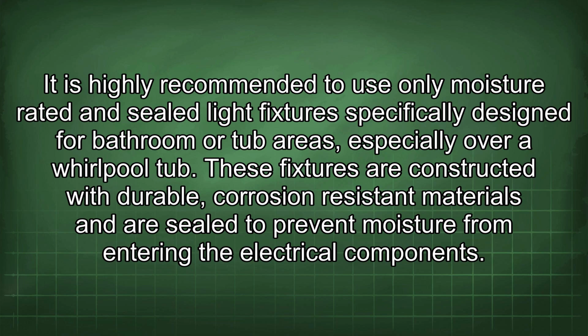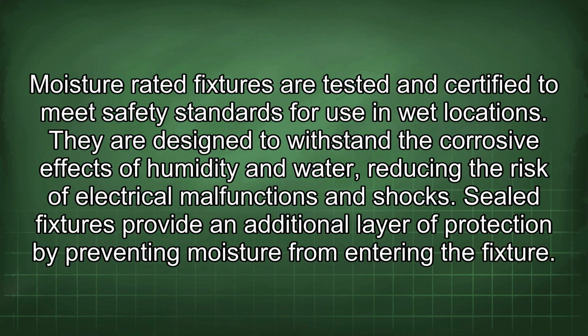It is highly recommended to use only moisture-rated and sealed light fixtures specifically designed for bathroom or tub areas, especially over a Whirlpool tub. These fixtures are constructed with durable, corrosion-resistant materials and are sealed to prevent moisture from entering the electrical components. Moisture-rated fixtures are tested and certified to meet safety standards for use in wet locations. They are designed to withstand the corrosive effects of humidity and water, reducing the risk of electrical malfunctions and shocks.